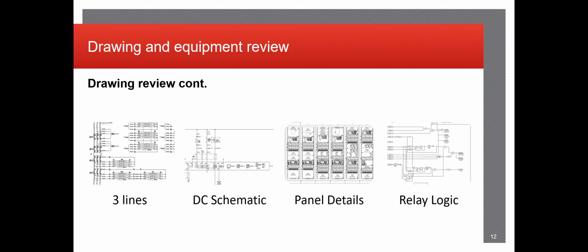Just a couple examples here. On the leftmost drawing is what we call a 3-line. That is pretty much a 1-line that shows all the phasing and sometimes, in this case, the equipment for current circuits and voltage circuits as well. The DC schematic you see in the middle left is usually what is involved in the relay functional diagrams, where you'll look at your circuits and verify functionality. The middle right is the panel details. We also call these front views in some cases. This shows you the physical layout of the panel that you may be testing or any surrounding panels for all the relay equipment, test switches, lockout relays, etc., etc.